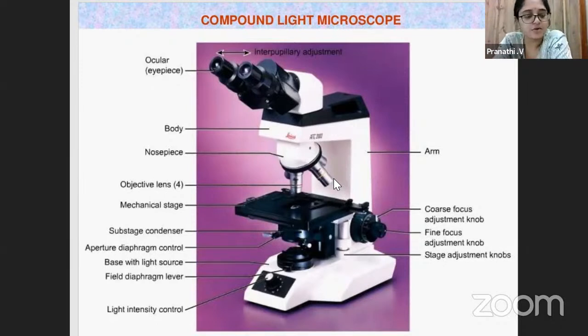So they also have a numerical aperture engraved on the mount. Typical value for the condenser's numerical aperture is 1.2. This can be attained only when the condenser is oiled. For different kinds of magnifications, it might become difficult to illuminate the field of view entirely with a condenser which is around 0.9 or more basically.